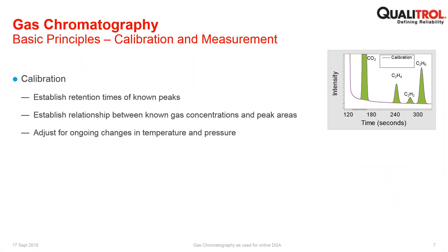So you can determine how much of it there is based on calibration. And one of the features of gas chromatography is that it must be calibrated on a routine basis. In a laboratory environment, it's usually once or twice a week, and in an online system, it's the same, twice a week. This provides some distinct benefits, and I'll talk about those a little later on. So calibration, first of all, establishes the retention times of known peaks.